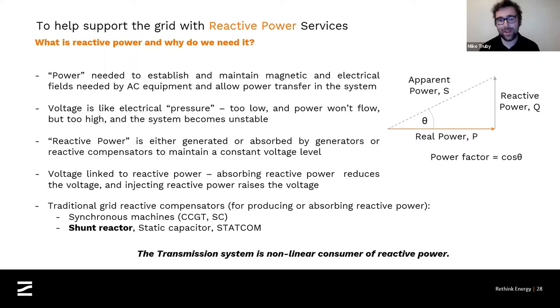A really important property of reactive power is that it's intrinsically linked to system voltage. If you have too much or too little reactive power in your system, your voltage starts to become unstable. And as Simon's already mentioned, it's really important for the stability and survivability of the national network that voltage can be regulated. In the traditional network, we had lots of synchronous machines that produce and generate reactive power as part of what they do. They're very stable, they're very slow to change. We also have a number of other devices that can be used to compensate reactive power, and the one that I'll particularly call attention to is shunt reactors, and I'll mention why in just a moment. These are sited at nodes around the country, next to substations or key strategic locations, to try and balance that reactive power and therefore keep the voltage stable.